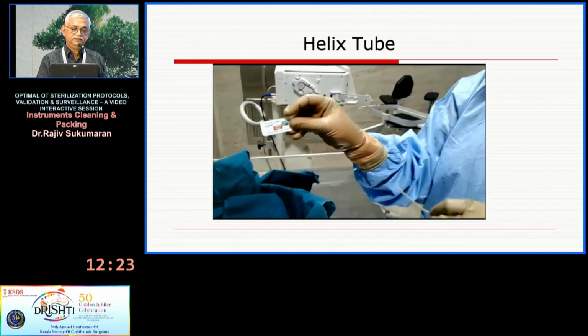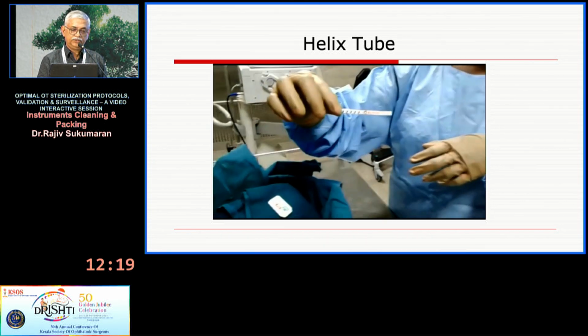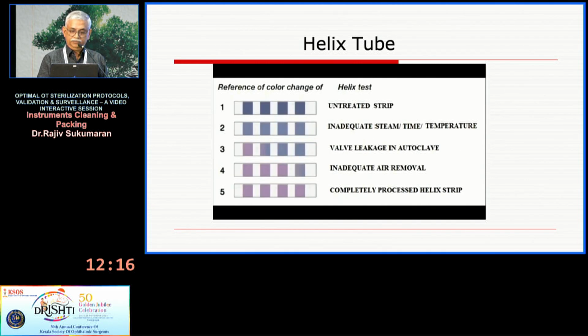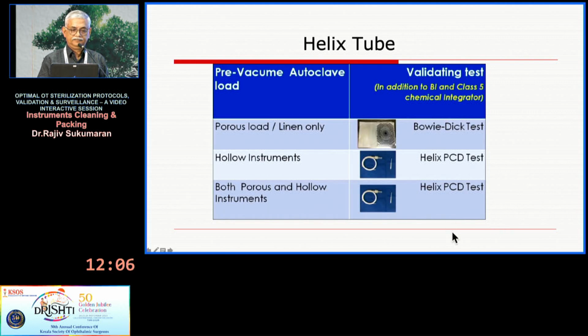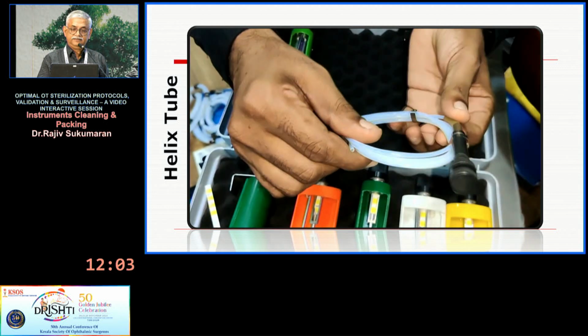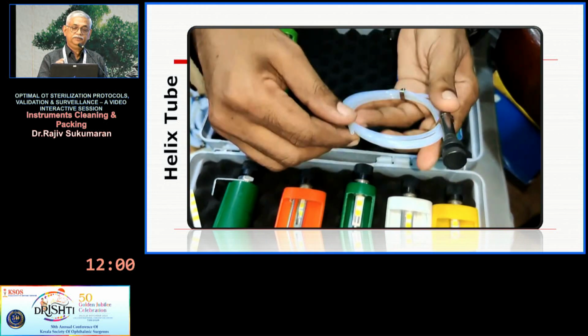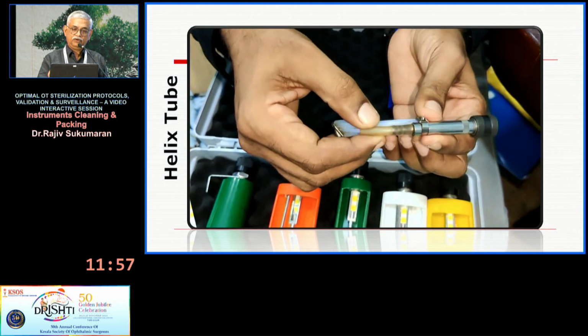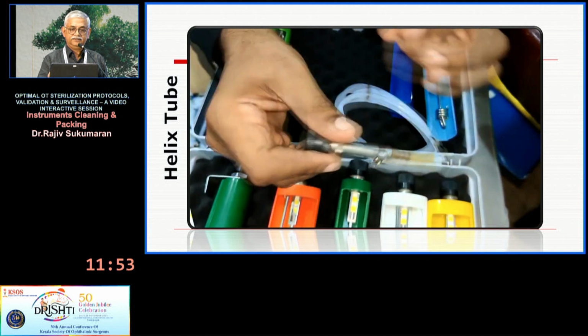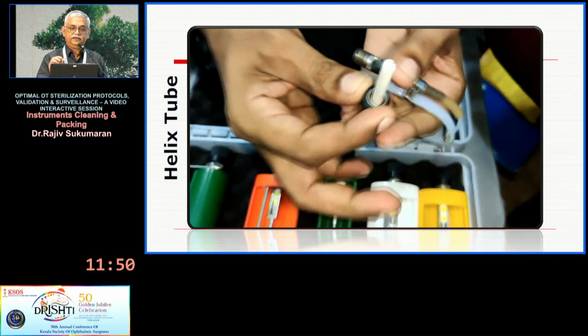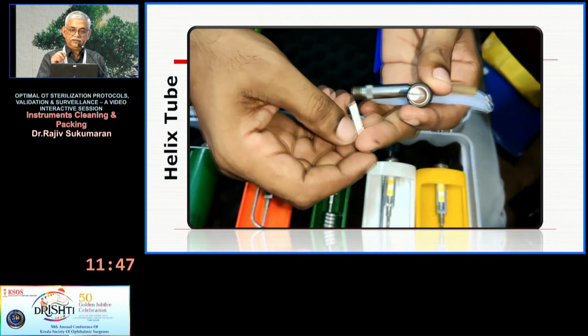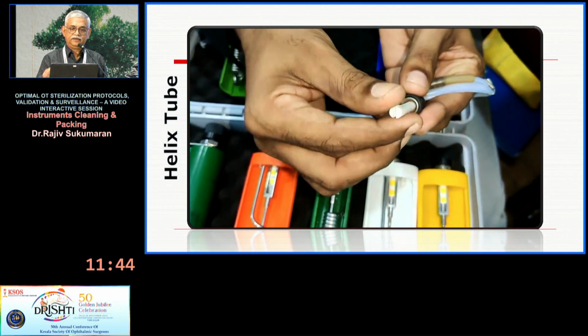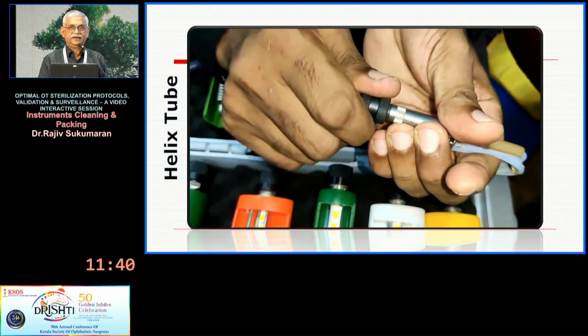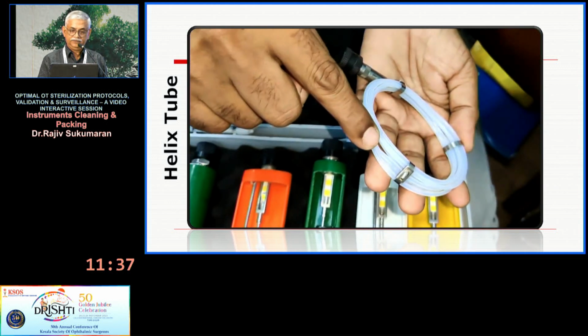the helix tube is taken out and you check the indicator. This is the class 5 indicator which I will be showing you again. This is the helix tube indicator. And if there is a leak or the vacuum is not clear, the color remains pink. Okay. And this is the best helix tube available commercially, which is made of metal. It's got a long tube, as I told you. That part of it is silicon, and the airtight component is because of a rubber seal there. This is what is recommended, but the plastic ones are also available.